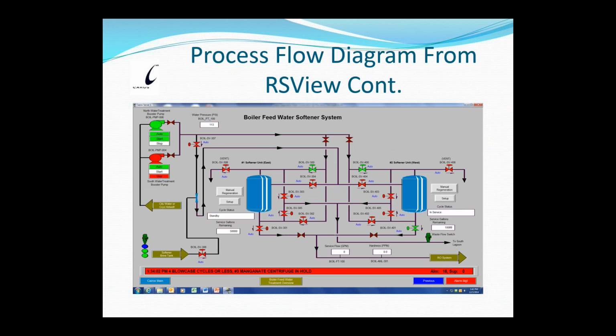So this is another screenshot of another part of the process, which, as you can see, here are the booster pumps that were shown in the last screen. If I were on this screen right now and I clicked where it says city water crystallizer hot well, it would take me back to that screen. Everything's all linked together in our process that way. But this just shows our two water softeners. Right now, when I took this screenshot, we had 0 service flow and 0 hardness, but it's going to the RO system. I'll explain why it's showing 0 service flow in another couple of slides so you'll understand why it does what it does.